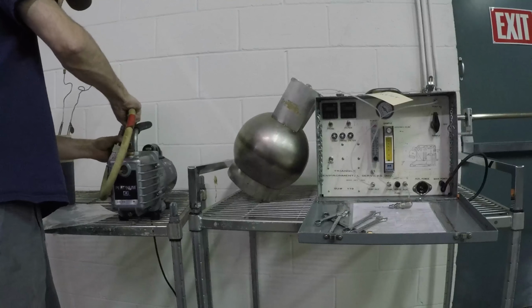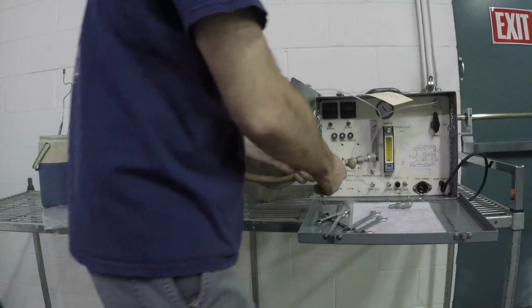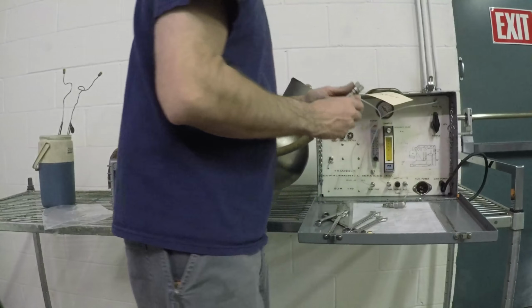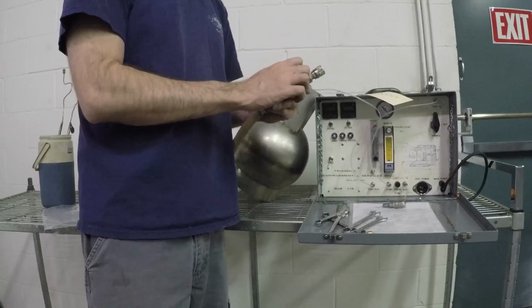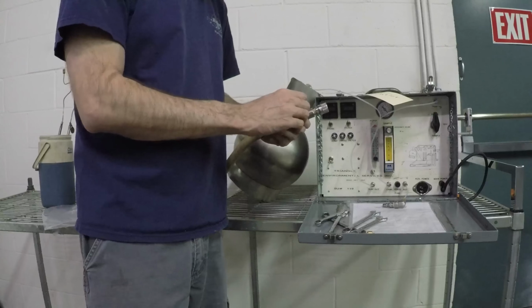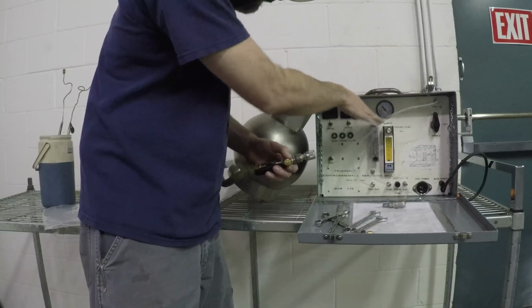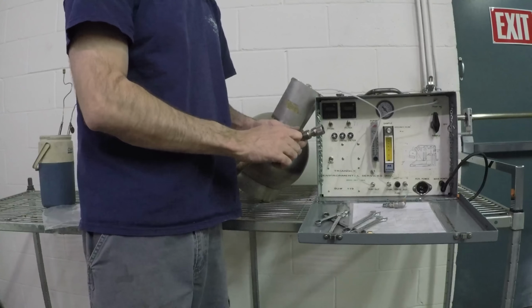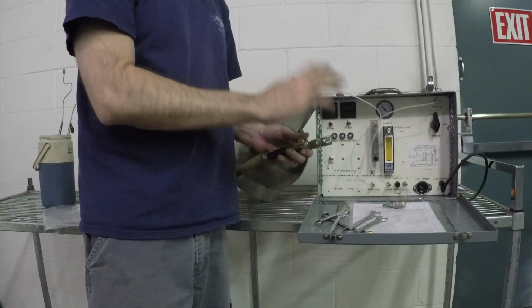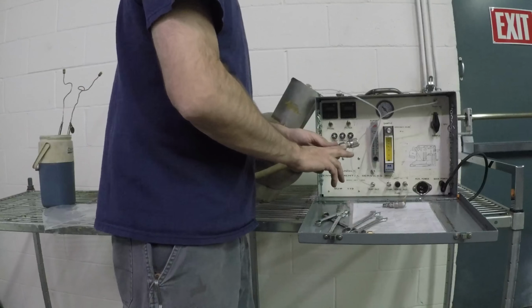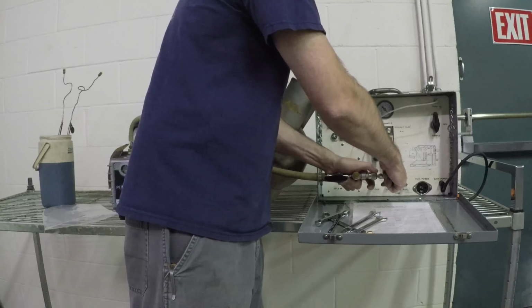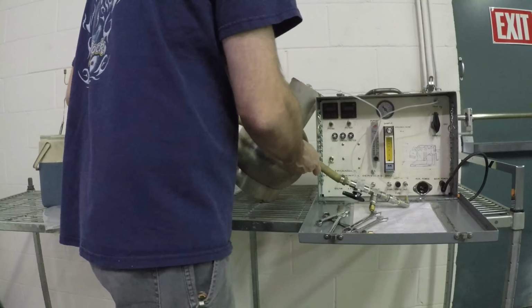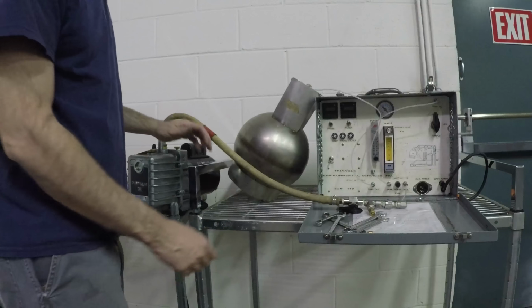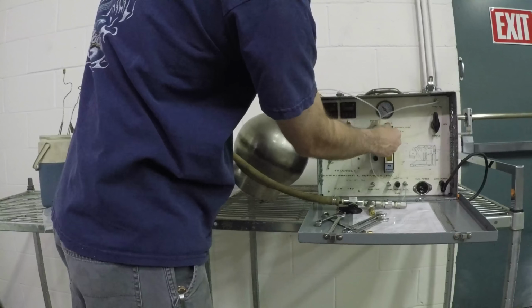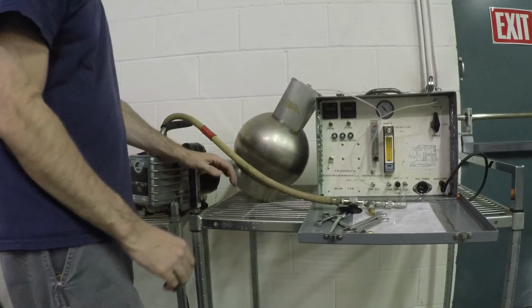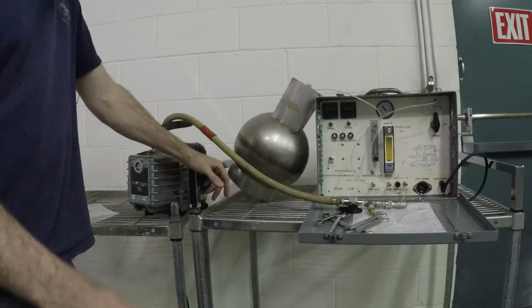line to it, turn it on, connect it. You'll have to supply your own manometer or gauge to read the barometric pressure. Our vacuum gauge is good for a reference, but it is not calibrated, and very often they get beat up in the field, so they're just good for a reference. Hook your manometer up here. Turn on the pump, turn it to sample, open the sample valve all the way, then you'll pull it down to a hard vacuum and wait for 10 minutes.